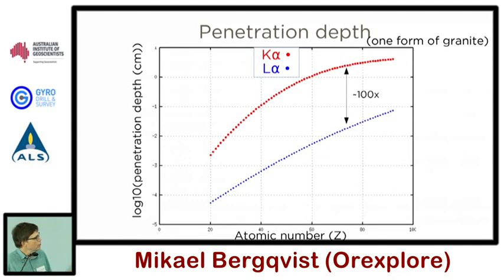So we have a quite powerful X-ray beam being emitted from the elements itself. That's because we are looking at the K peaks and not the L peaks. Also, regarding the question in the last session about overlap, by using the K peaks, where it's possible for the heavier elements, we can avoid some of this overlap. It's a very crowded place amongst the lighter elements' emission lines or peaks.